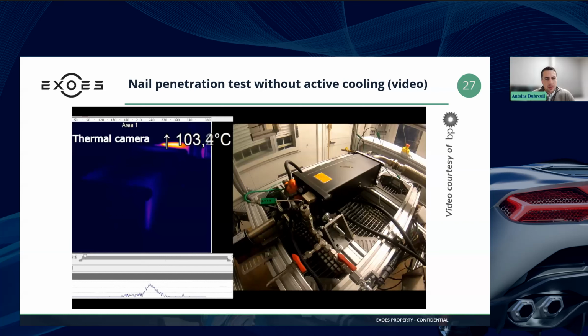Yeah, thanks Cecile, that's a good point. Here we're trying to put ourselves in the worst possible case, where we'd have a double failure. So in addition to having a failing cell going into thermal runaway, we also mimic a failing pump, so the coolant pump wouldn't be working. We want to make sure that as a passive system, it's sufficient to prevent the propagation of thermal runaway. Here you can see the temperatures have gone down below the 100 degrees Celsius mark, and they'll continue to go down towards a successful outcome, as there has been no propagation of thermal runaway in that case.